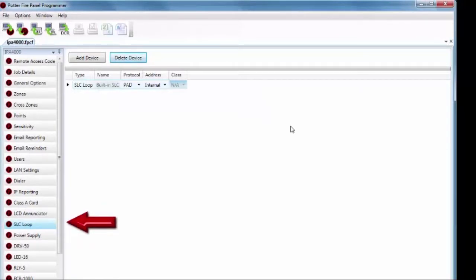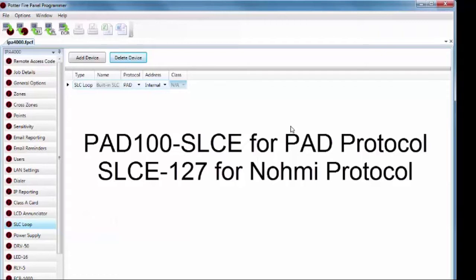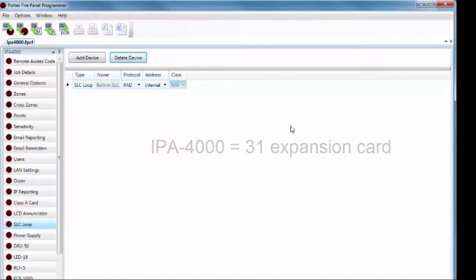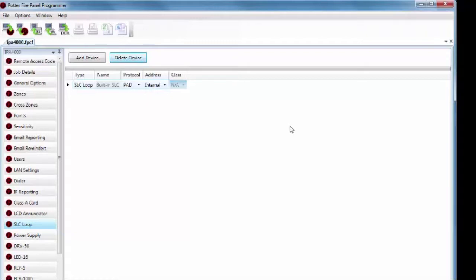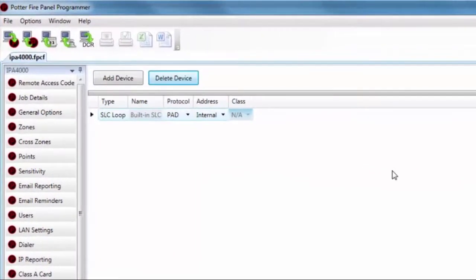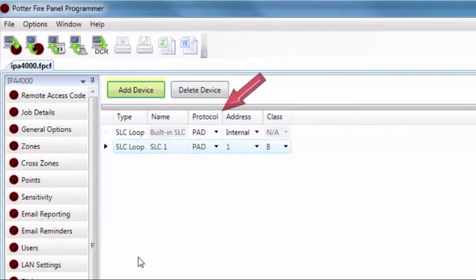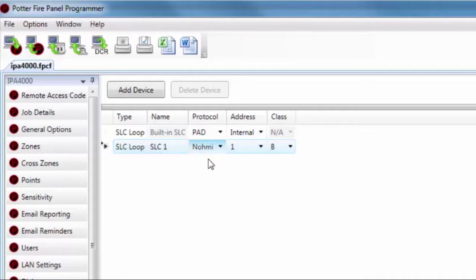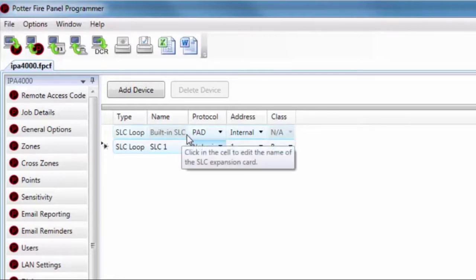Moving to the SLC loop — this is where you can add SLC expansion cards, either the PAD 100 SLCE or the SLCE 127. On the IPA-4000, you can install up to 31 SLC expansion cards for either the PAD protocol or the Nohmi protocol. Click Add Device to add an SLC card. For each SLC loop, you can select the protocol — choosing between PAD or Nohmi. PAD protocol indicates use of the PAD 100 SLCE expansion card, while Nohmi protocol indicates use of an SLCE-127 expansion card with Nohmi protocol devices.